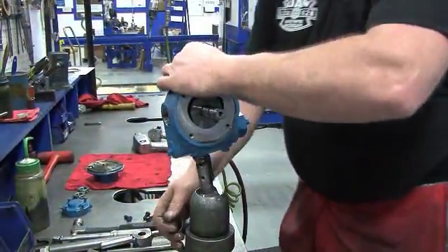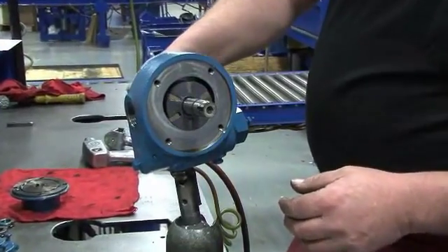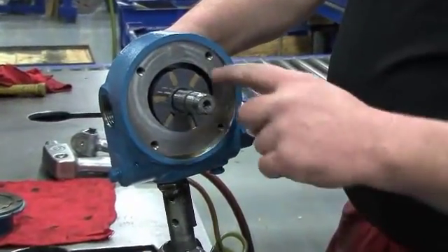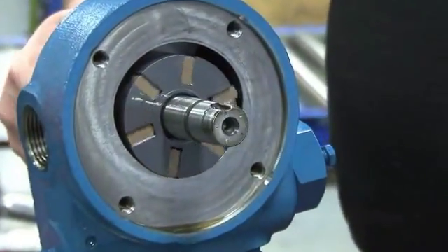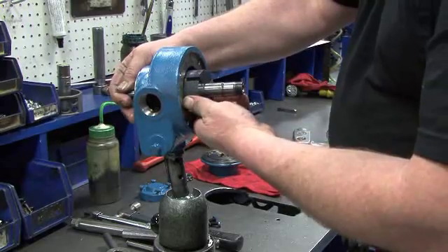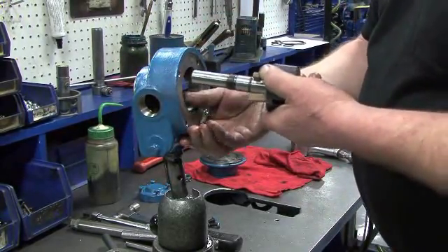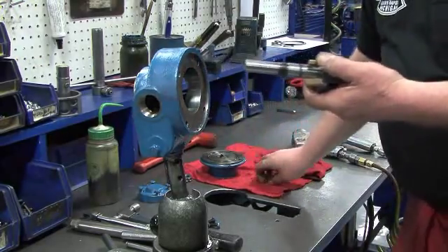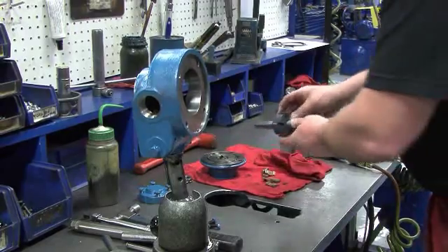Turn the pump around. On this side of the pump you can see the rotor turn with the shaft as the shaft is turned. Installed in the rotor are six directional vanes, which are loose inside the rotor assembly. Gently pull the rotor and shaft from the cylinder — as one hand is pulling the shaft, the other hand should be cupped underneath the rotor to prevent the vanes from falling out. Set the rotor, shaft, and vanes to the side.